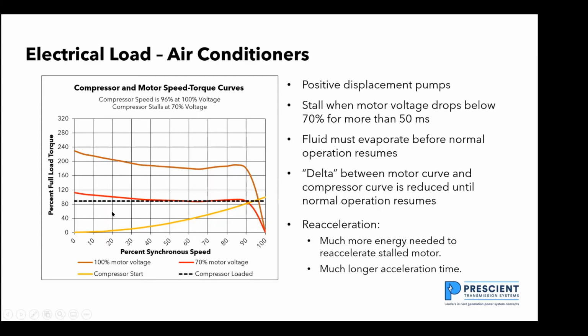And the problem you have is when I'm looking at a fan and I'm at 70% voltage on the motor, at low speed I've got a lot of difference between the fan curve and the motor curve. When I'm looking at an air conditioner motor where I've got fluid that I'm trying to evaporate, I've got a very small delta between the torque that's needed and the torque that's available.